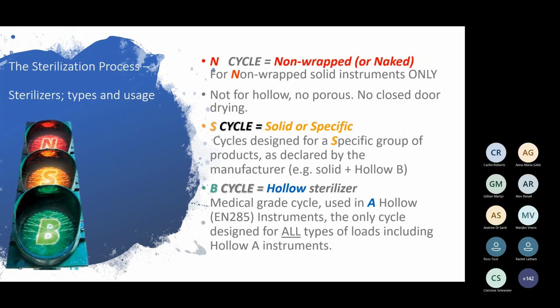S-class cycle is one of the ones that most of you in the medical world will have. These cycles are designed for a specific group of products as declared by the manufacturer. So once again, you need to be reading the instructions for use from the manufacturer. Generally, they'll be solid instruments and hollow B items. A B-class sterilizer is the ultimate sterilizer that can process hollow A loads, and that's more used in dental, for small hollow tubes like dental handpieces, those sorts of things. Pretty rare to use them in medical practices. You need to understand what type of instruments you have when you're buying a sterilizer, so you choose the right sterilizer.